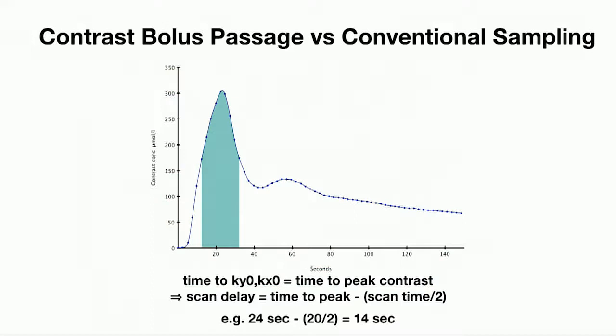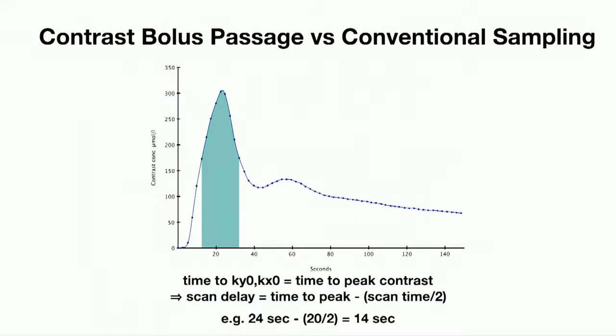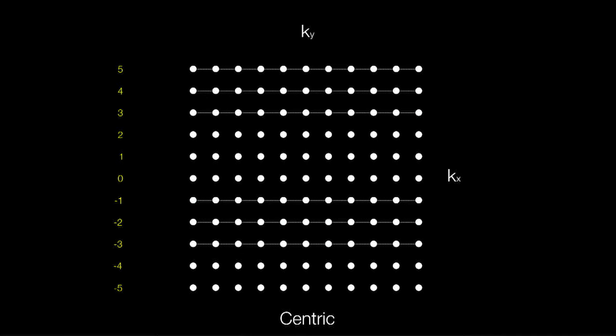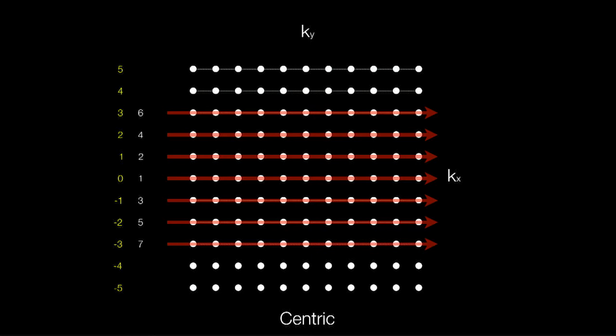This led to the idea that we would sample the centre of K-space earlier on — front-loading it. That allows us to move to what we call centric encoding, and we can then move to fluoroscopic triggering where we can actually watch the contrast coming in and start the scan when the contrast is in the right place. The idea is that we do the central line first and then go either side all the way out to the edges of K-space.